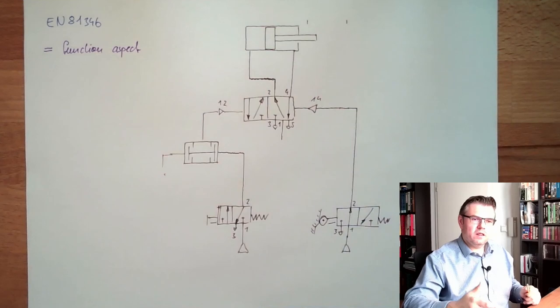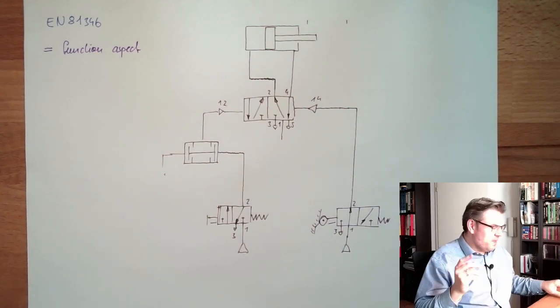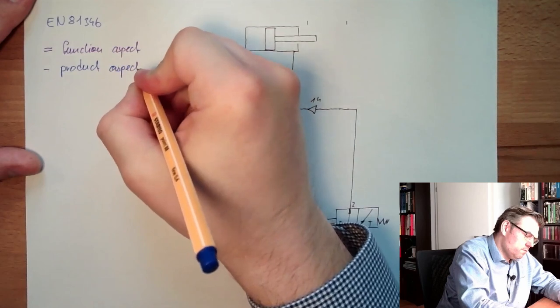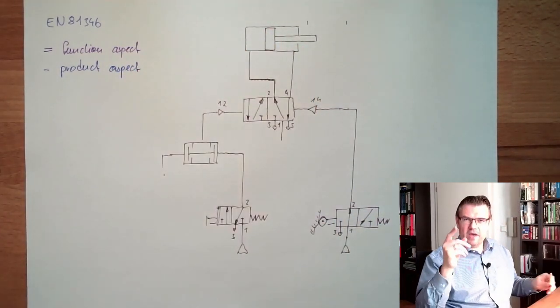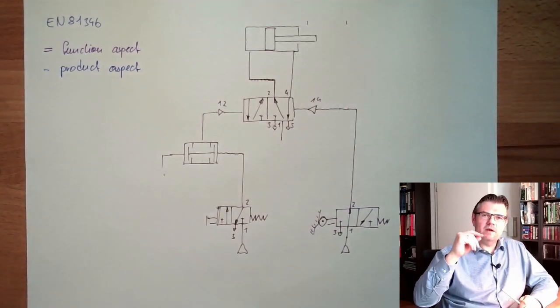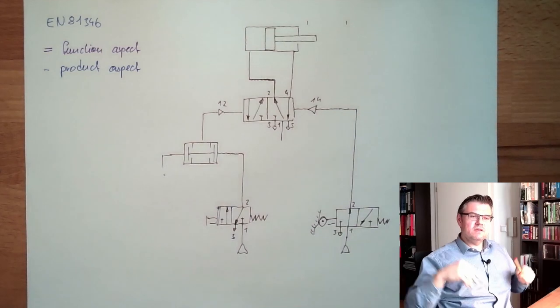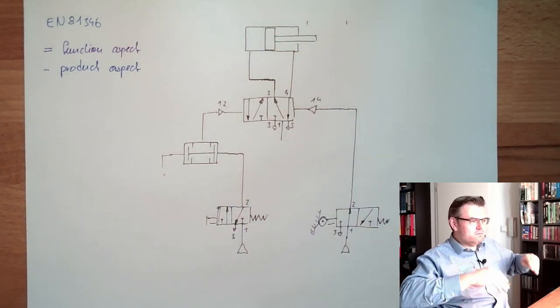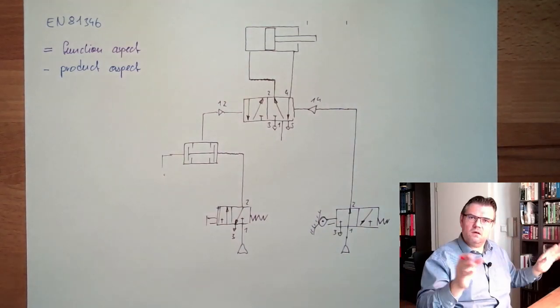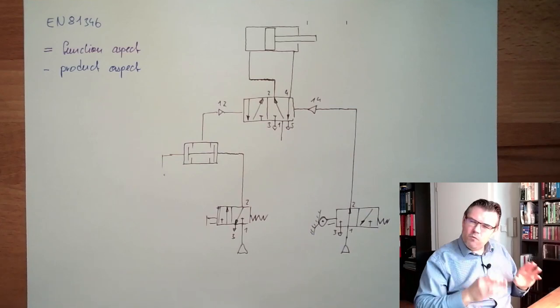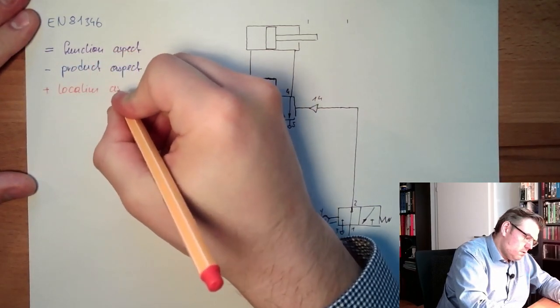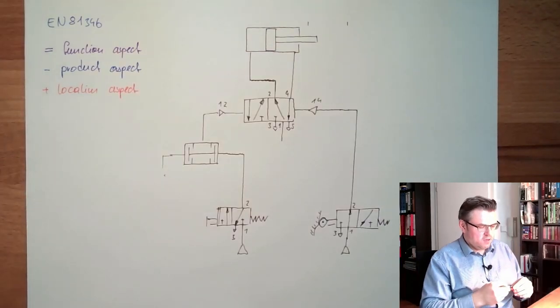Then there is the product aspect, usually started with a minus sign. And then there's also the location aspect. If I want to have coded in my name where this thing is used in my whole system, if there's a big plant, it might be interesting that you know this is a part which belongs to the heating system or the governing system of the turbine or whatever. This is the location aspect, usually started with a plus.